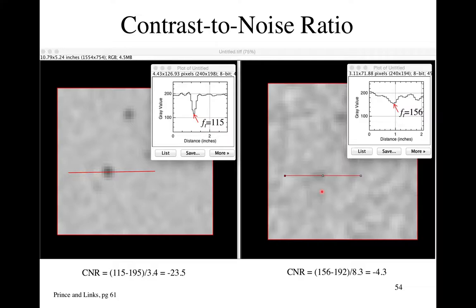Student question: when characterizing your system's signal-to-noise using a phantom, do you have to do it with different types of tissues or materials? The answer is yes — specifically in X-ray, different materials attenuate X-rays differently and modify the energy spectrum of the beam differently. Where an object is in the field of view actually matters for these parameters. It's quite complicated in CT and X-ray, but less so in NMR.